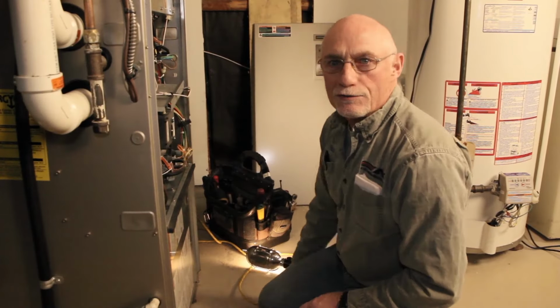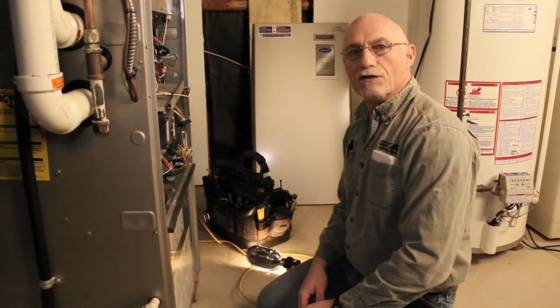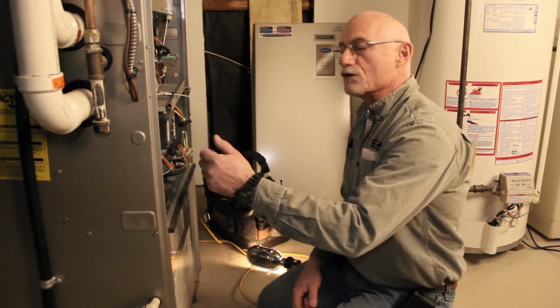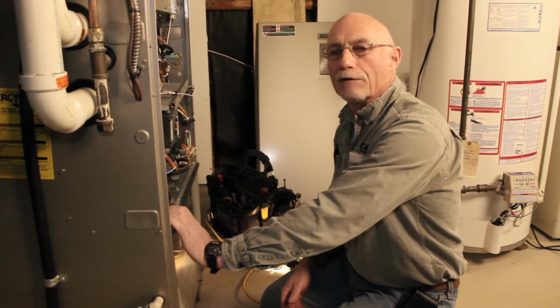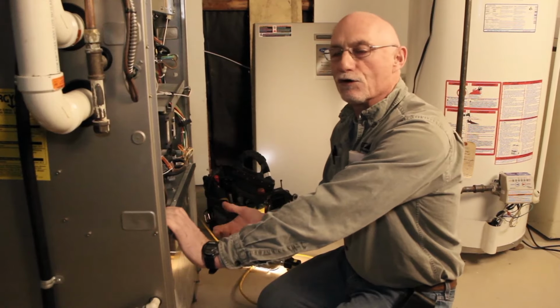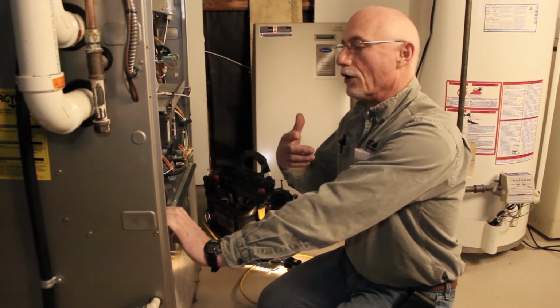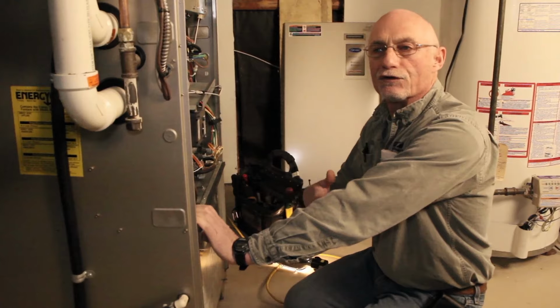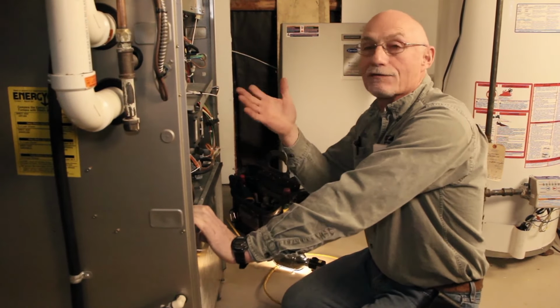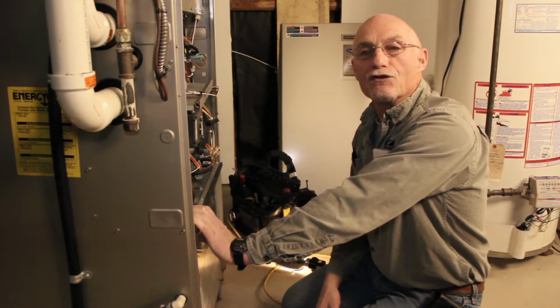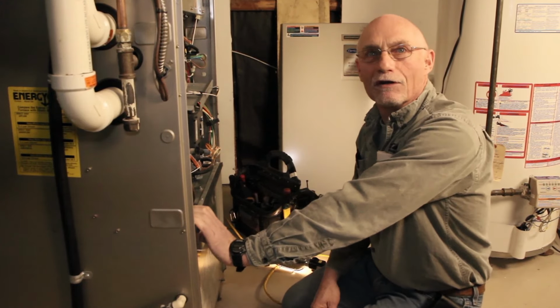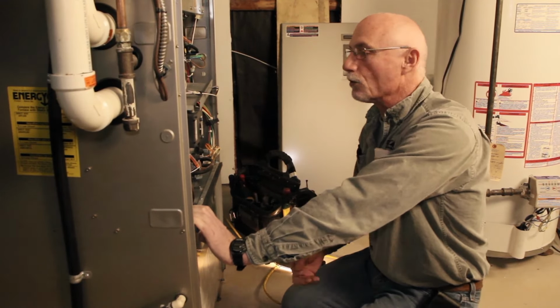Just so you know, today's modern furnaces, they have all these different safety switches, and one is called a high limit switch, that if the furnace fan motor burns out or your furnace filter gets too dirty, this high limit switch will open up at a certain internal temperature within the furnace, and it shuts your furnace down and says, hey, we're running too hot. And that's the importance of having a clean filter and not restricting ductwork.